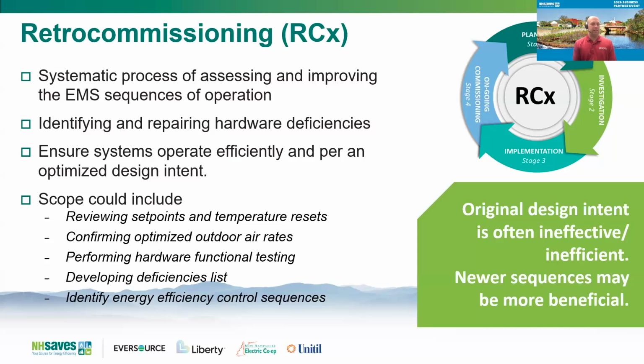the current design intent. Retrocommissioning may include identifying and repairing hardware deficiencies, right? Putting together a deficiencies list. You look at the air handler and you open up the panel, and all of a sudden the outside air damper actuator is hanging in the duct, right? It's not connected. Well, clearly that's not going to be able to modulate the outside air damper. So you've got not only inefficiencies, but you've got issues with hardware. You want to ensure systems operate efficiently and optimize.